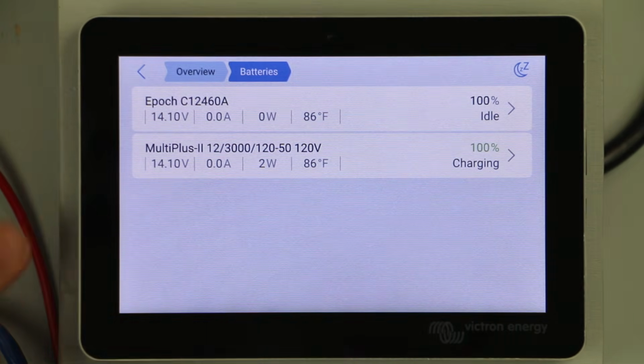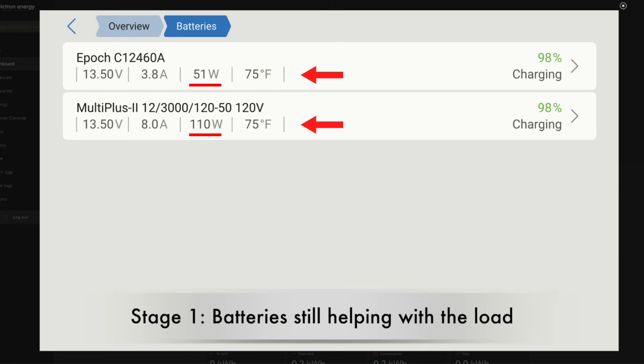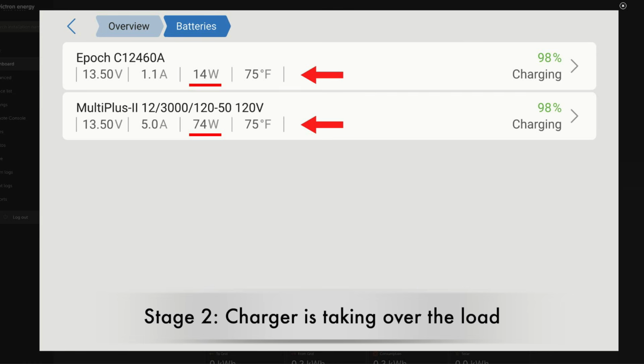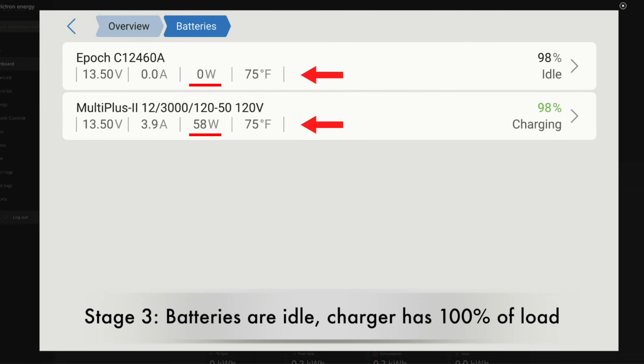It was 14.2 during absorption, and it's basically going to stay at 13.5 as long as the charger stays on, and eventually the batteries are going to fall to that 13.5. They'll supply power to any loads that come online, but once they hit 13.5, they're going to sit there, and the charger takes over supplying that 13.5 volts to any DC or AC appliances. The batteries just sit idle, and you can leave them like that for days or weeks at a time. It's really good because it won't cycle the batteries, and they'll be ready when you shut off your charger or unplug from the power grid — fully charged and ready to go, without cycling during those days and weeks you're plugged in.